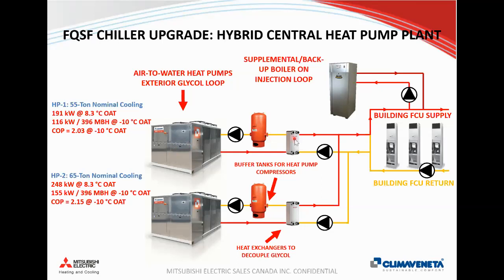So the way this was configured in the building was with heat exchangers to decouple glycol from the entire building. They didn't want to have glycol running through the building, just the cost of filling up that system with glycol plus the cost of operating pumps with higher energy consumption. So they interface that with heat exchangers. So essentially the main building loop comes back, and then based off the building automation, they're basically at the heat pumps dumping heat into the building loop, going to the fan coil system.